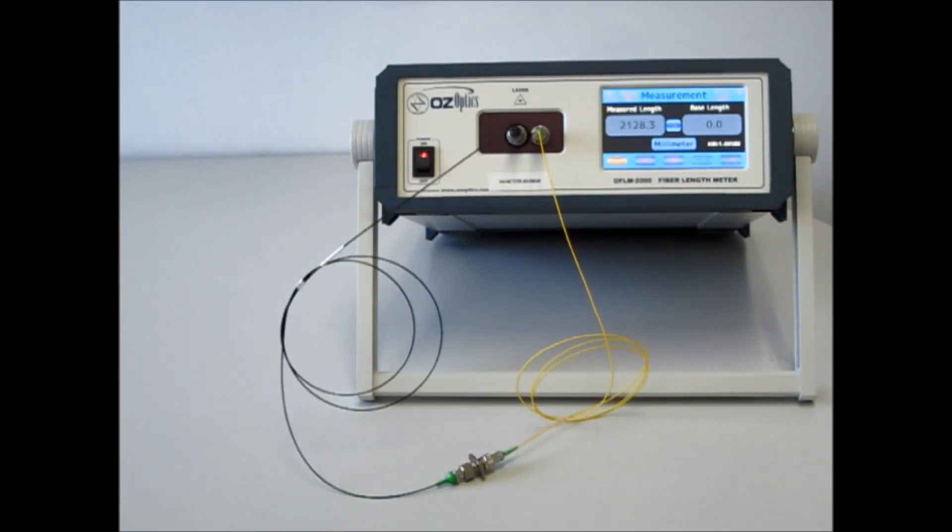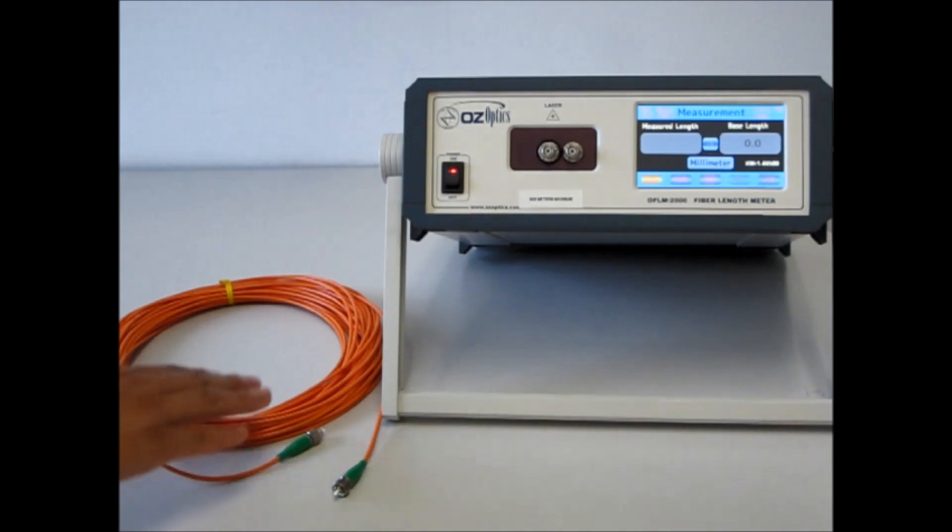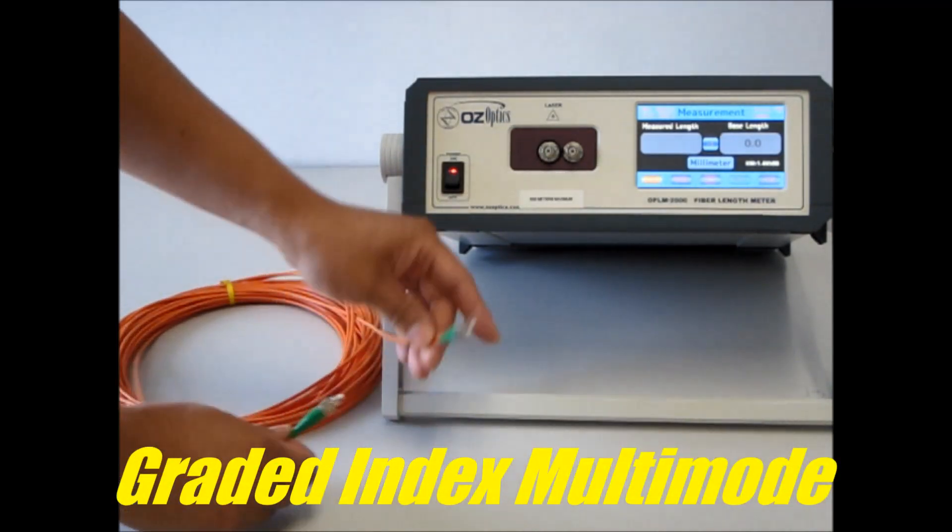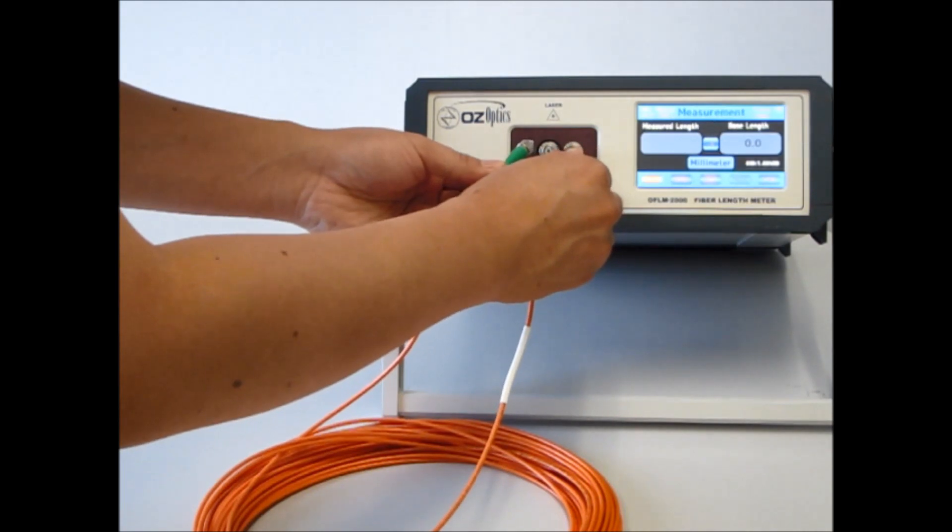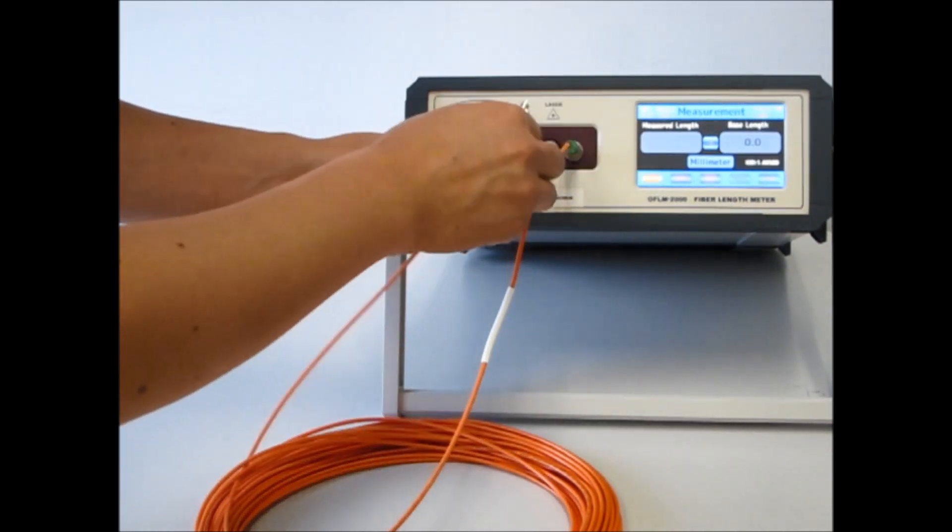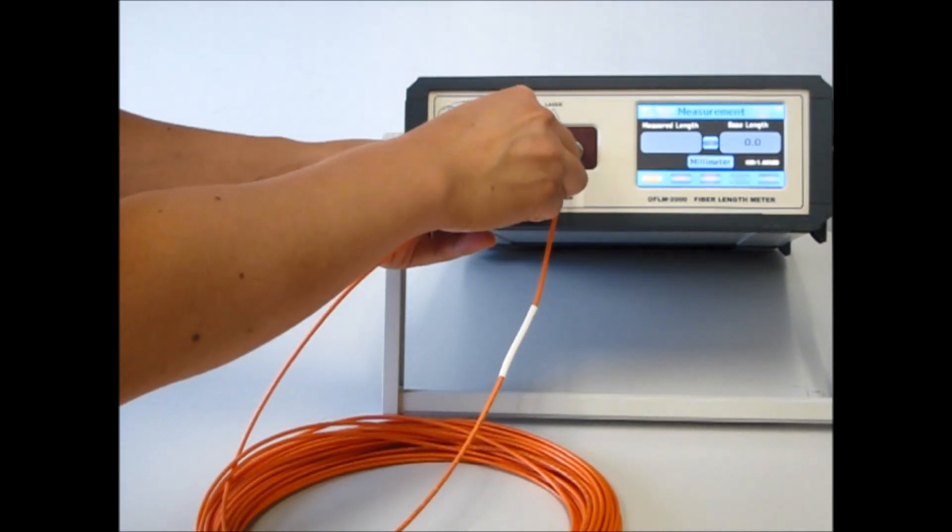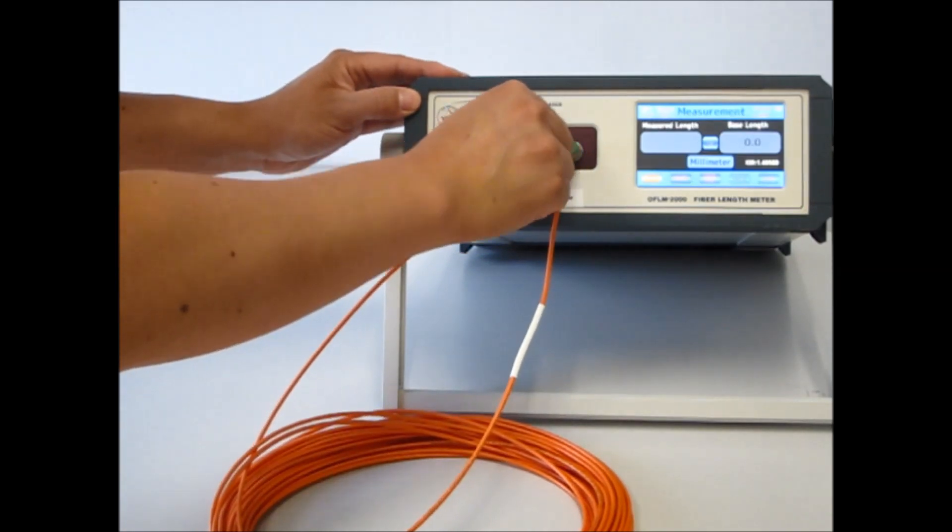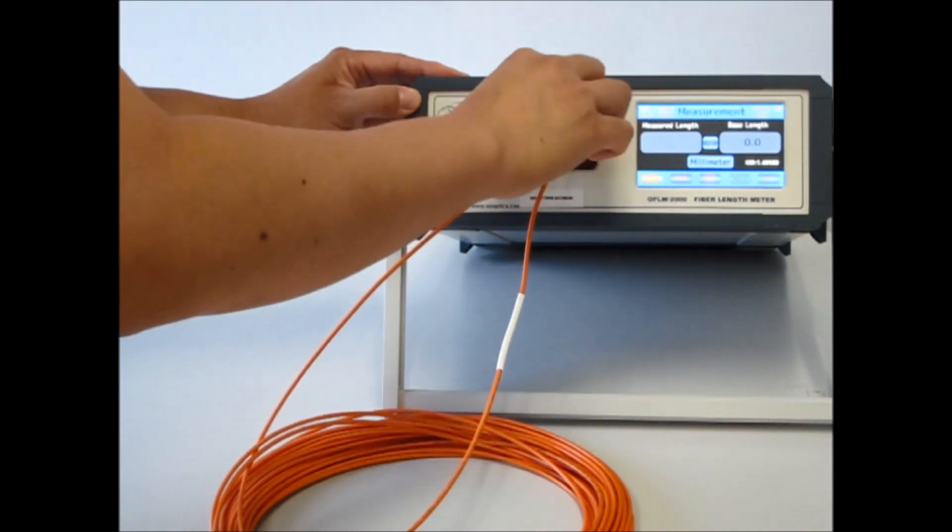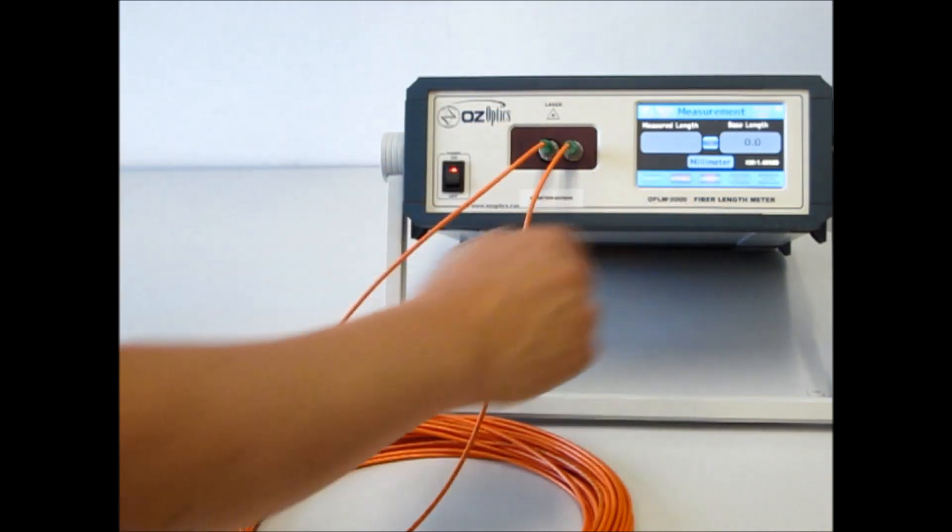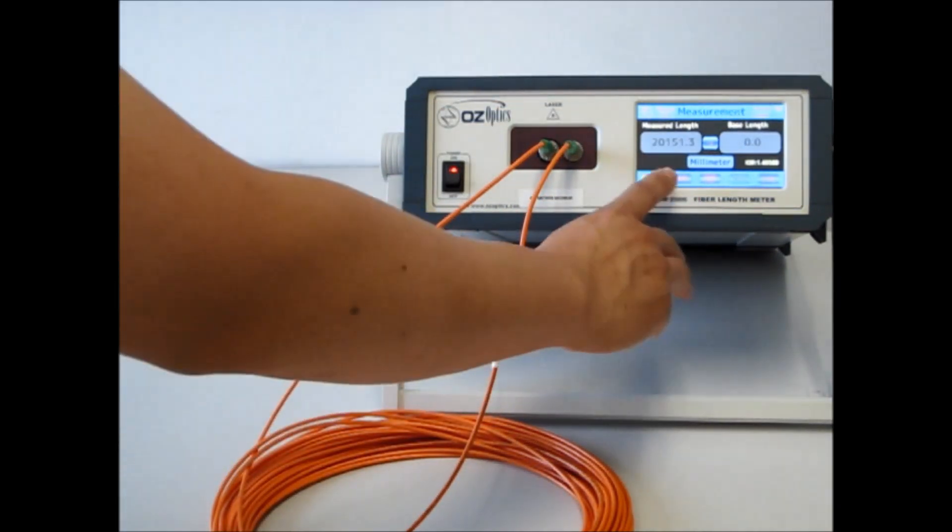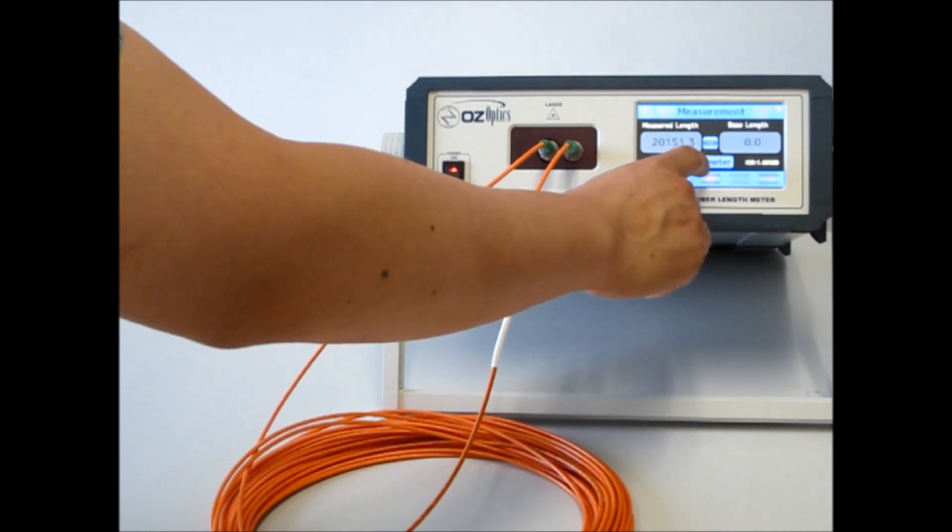Now that you've seen the key functionality of the fiber length meter, we'll demonstrate the various fibers and lengths that it can measure. This orange patch cord is a graded index multi-mode fiber with APC connectors on both ends. Plugging this one in and tightening up the connections, then pushing the run button, you'll see that this patch cord is 20,000 millimeters long, or 20 meters if you prefer.